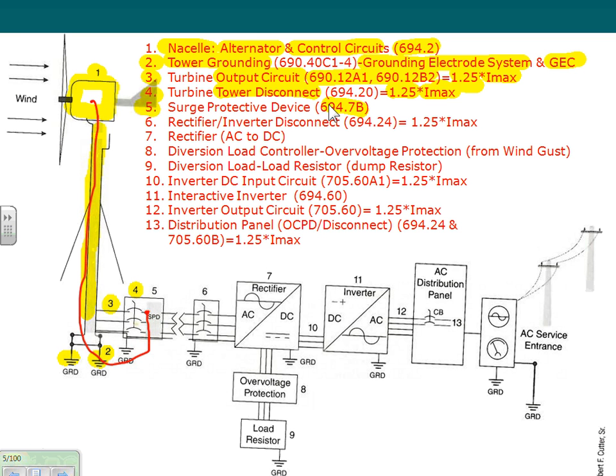Okay, this is a good place where we require surge protective devices. We all know, guys, if you get hit by lightning, a surge comes into the system. This surge protective device is supposed to take that huge amount of current, suck it down to Mother Earth, and hopefully save your equipment. This is the only place that I know of where a surge protective device is required. I can't recall any other places out of memory. Any comments, guys, about this one? Taking that pulse from the system directly into Mother Earth.